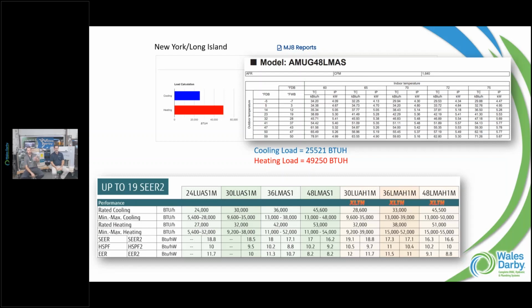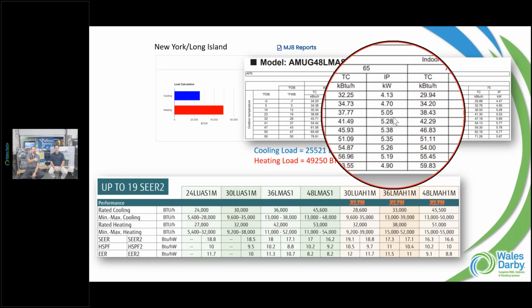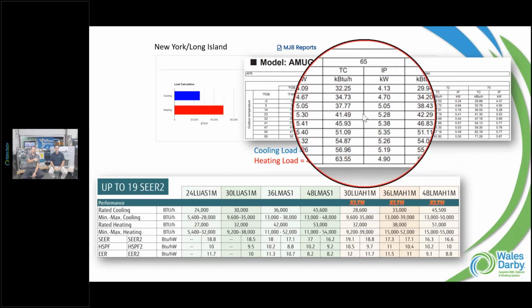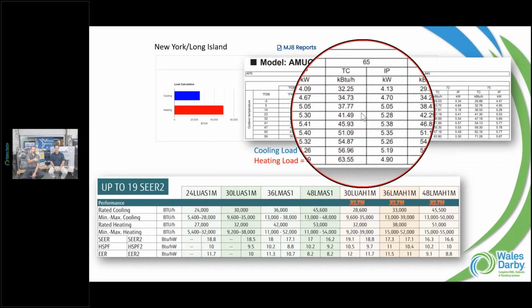But even if this was going to take care of most of our heating, you know these numbers. How often is it 14? It's so rare. Exactly. When we look at our bin data, most of our winter where we are is in that 40-degree range. You should do 32. Yeah, between 32 and 40, even going up to 70. So if we're looking at 32, that is 46.5, so we're right about 45,000.